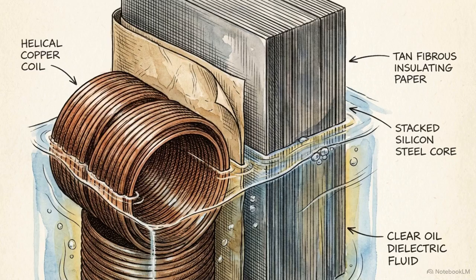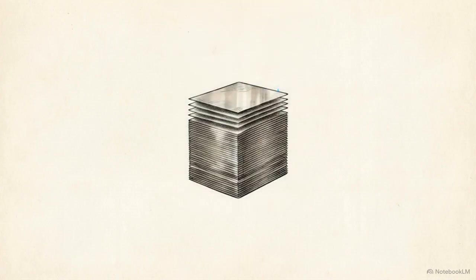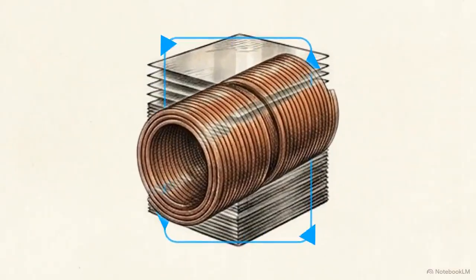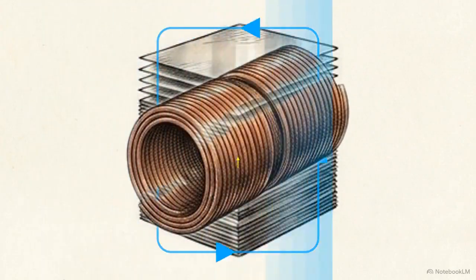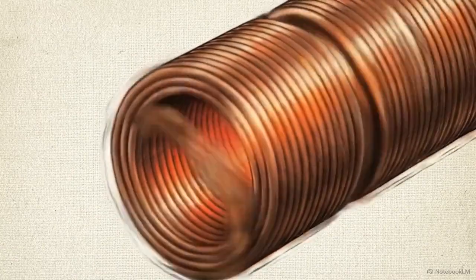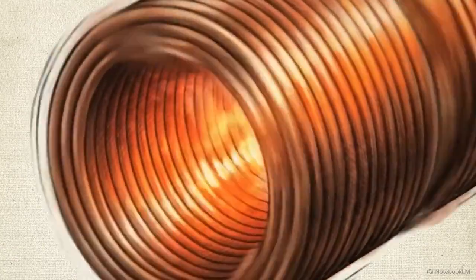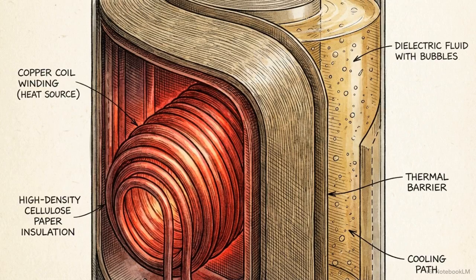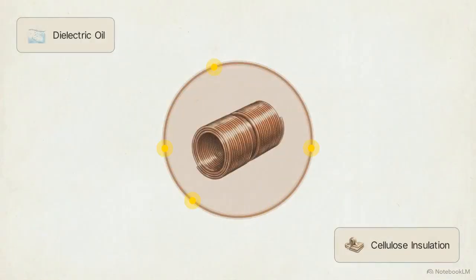Each material plays a highly specific physical role. The silicon steel is stacked to efficiently generate and channel a concentrated magnetic field without wasting energy as heat. The precise geometry of the wrapped copper coils determines how they intersect with that magnetic field, successfully inducing a new current inside the secondary winding. Pushing current through the resistance of the windings and forcing magnetic flux through the core generates an intense, catastrophic thermal load. To prevent the system from destroying itself, the cellulose and the dielectric fluid work in tandem. They suppress high-voltage electrical arcing while rapidly absorbing and dissipating the internal heat.